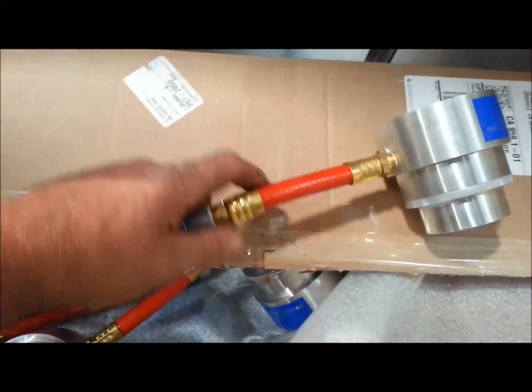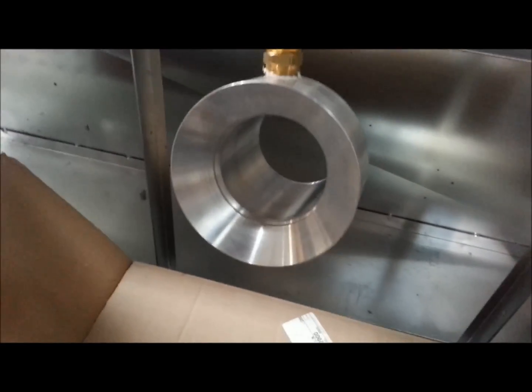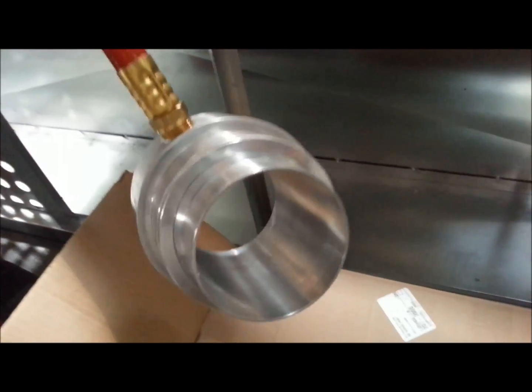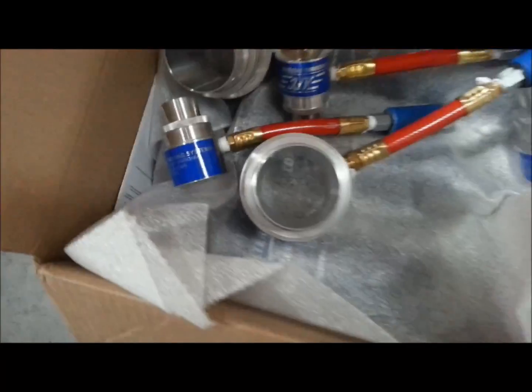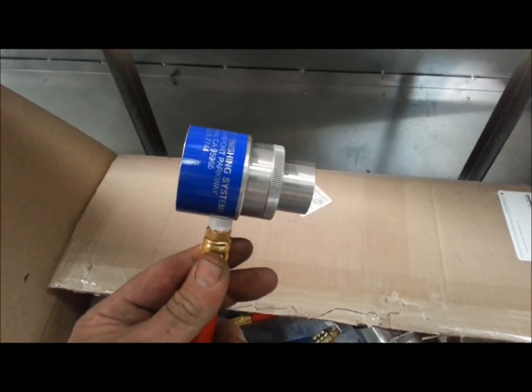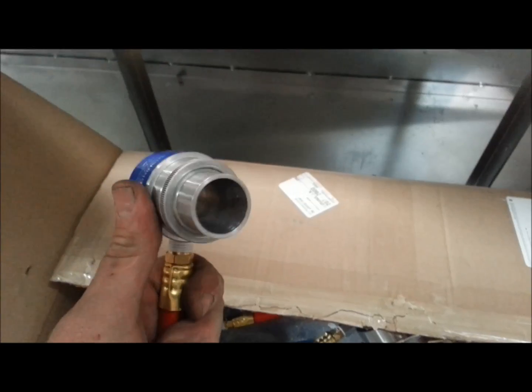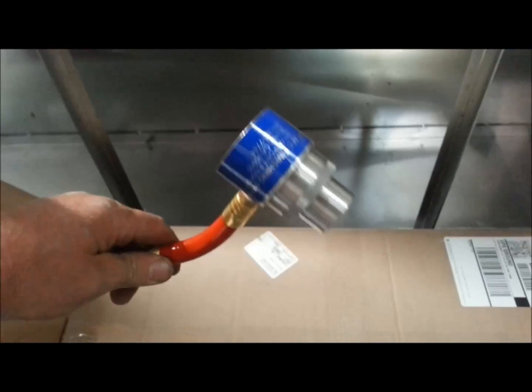These hoses are what's called a stay-put hose — if you bend them, they stay there. So these get mounted in the walls, with the intake in the back and they discharge the air out front. There are four large ones, which create a fan-type pattern, and four smaller ones that are kind of a pencil beam — they shoot the air about 20 feet. And with the stay-put hoses, you can angle them and aim them at whatever you want.